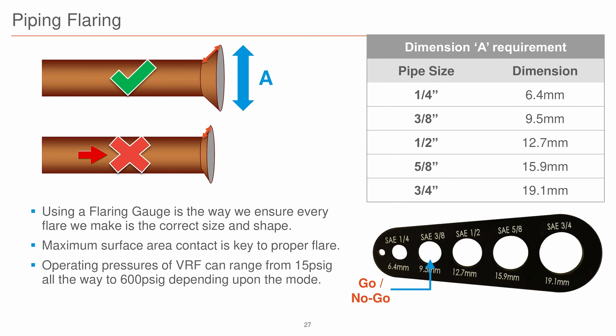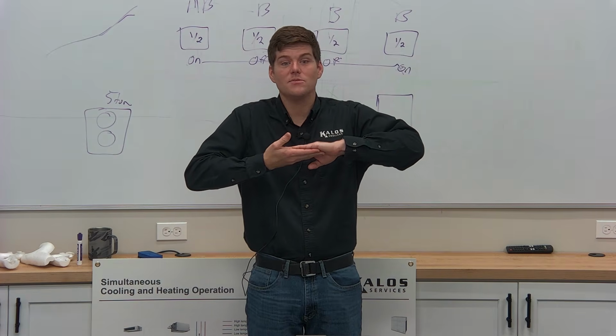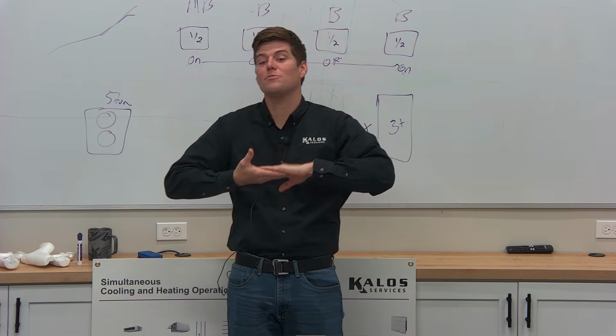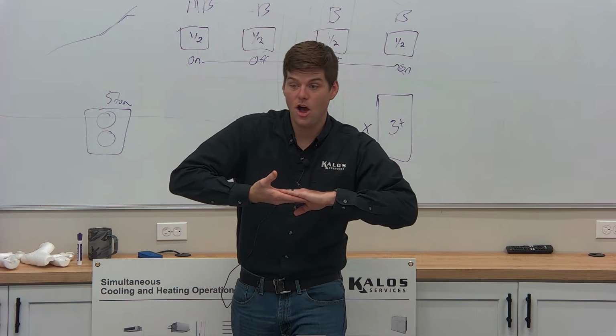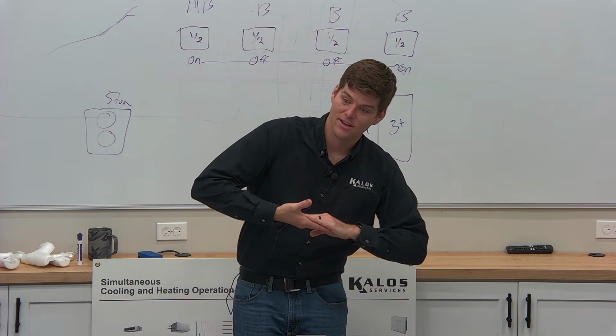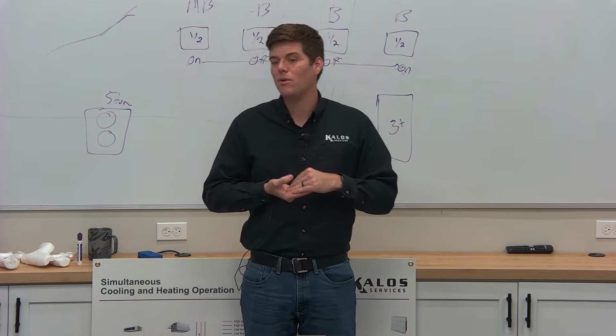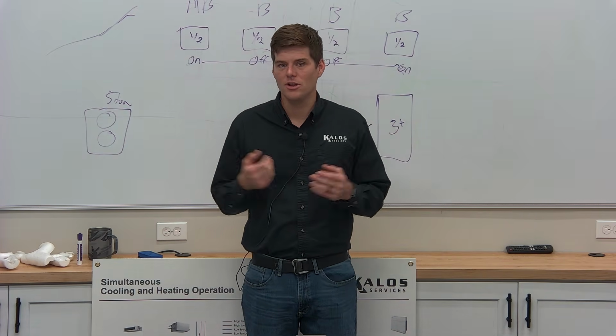But you can see on that X line how short that flare is. That surface area is extremely small, as opposed to the actual correct flare, which is on the top side. If you used a flaring gauge, it would have passed right through, and it would have told you it's not the right size. The top one has an increased surface area, which is actually designed to make sure that is a sound seal. Because these systems can operate upwards of 600 psi, right? All the way down as low as 15 psi. It all depends on the mode, the climate, where you're at, what it's doing, charge.